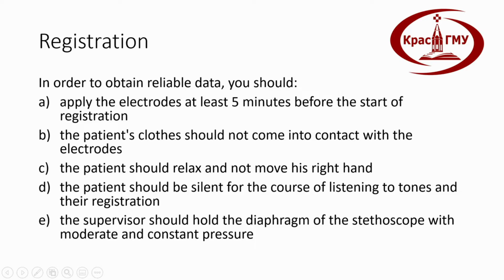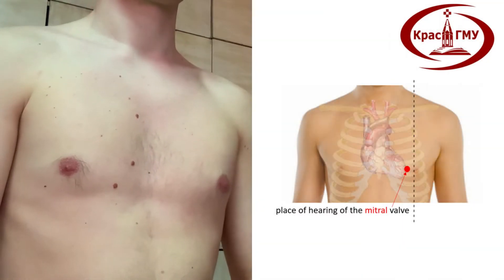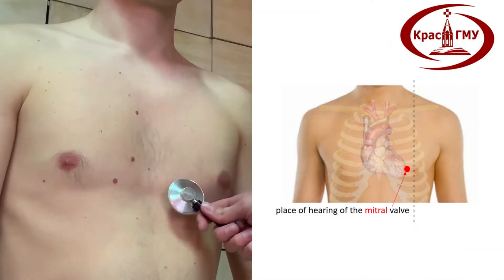Registration: In order to obtain reliable data, apply the electrodes at least five minutes before starting registration. The patient's clothes should not come into contact with the electrodes. The patient should relax and not move their right hand, and should remain silent during the listening and registration of tones. The supervisor should hold the diaphragm of the stethoscope with moderate and constant pressure.